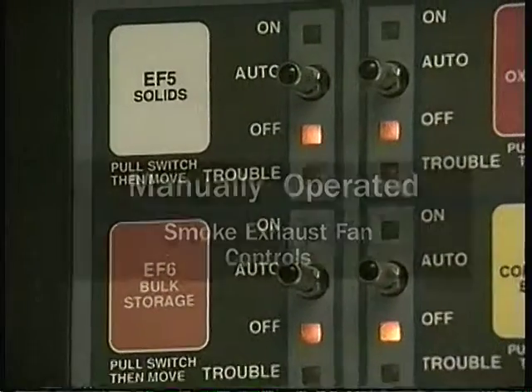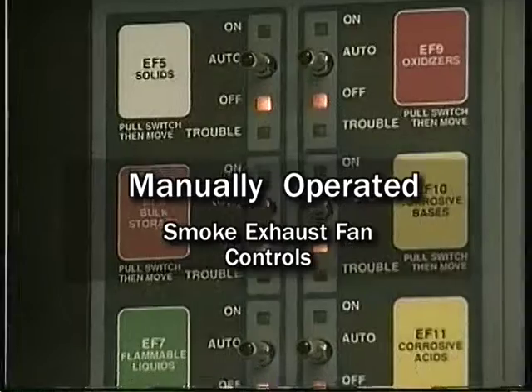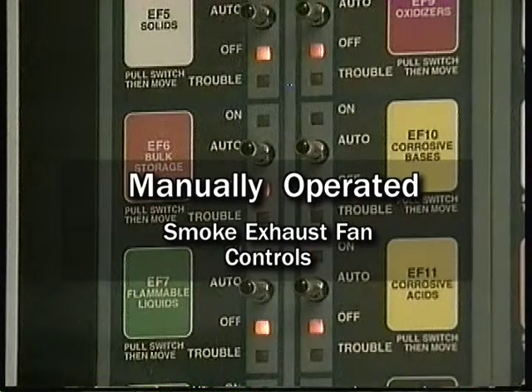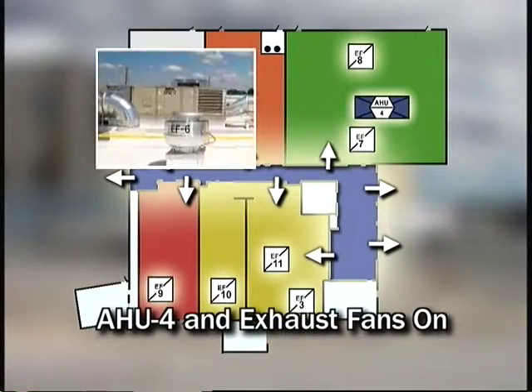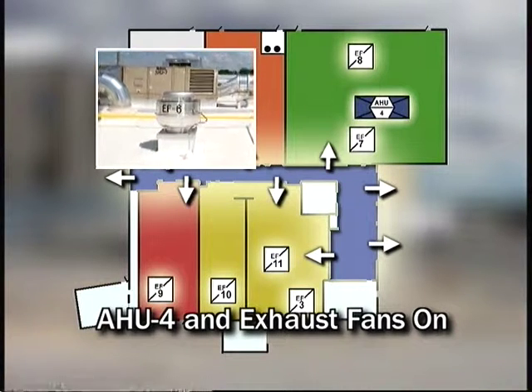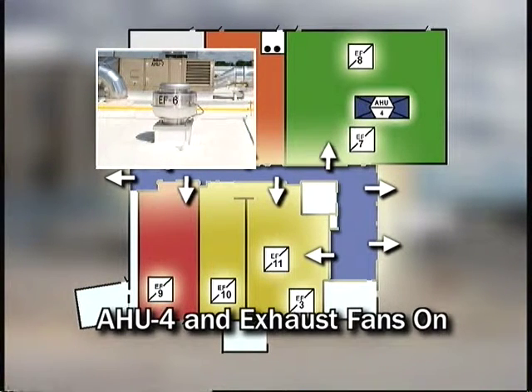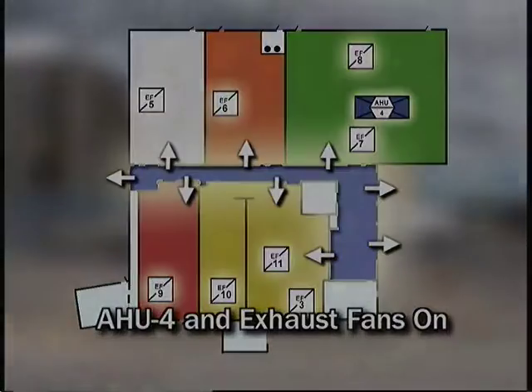Also located near the fire alarm panel are controls for the smoke removal fans. These manually operated fans may be used in conjunction with the air handling units to remove smoke in specific areas of the building. For example, use of AHU 4 to pressurize the corridor areas with smoke removal fans on and smoke vents open will force air out of the core of the facility.